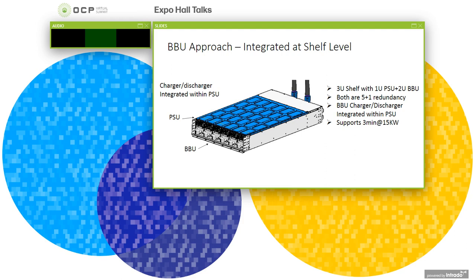Here, charger-discharge circuits are integrated within the power supply, so BBU is a simple battery pack with BMS control board only. The major advantage of this design is BBU thermal performance, because it does not have a major heat-dissipating power converter within its chassis. The PSU shelf is on top of the BBU shelf, but there's very limited thermal impact because they are not in the same chassis. However, with this design, BBU cannot operate standalone because there's no charger-discharger built into its own chassis.